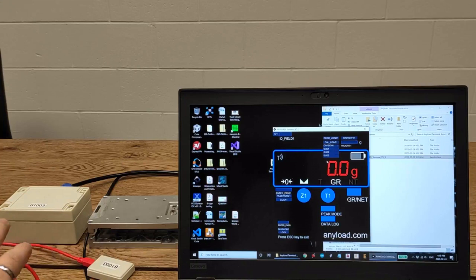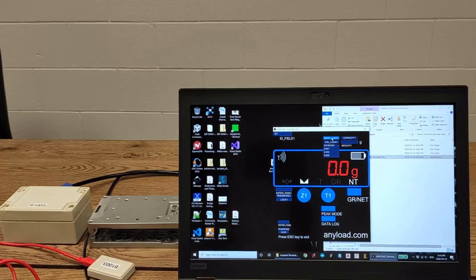and make sure there's nothing on the load cell and press dead load. So it's zero.